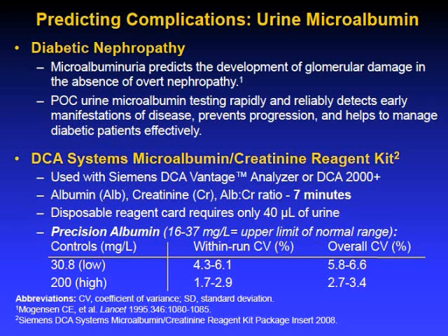The precision of the assay was determined by multiple DCA 2000 microalbumin and creatinine assays of 2 different commercially prepared artificial urine-based controls that were performed by 3 independent investigators. Within-run precision was evaluated by including low and high controls in duplicate in each run of clinical specimens.